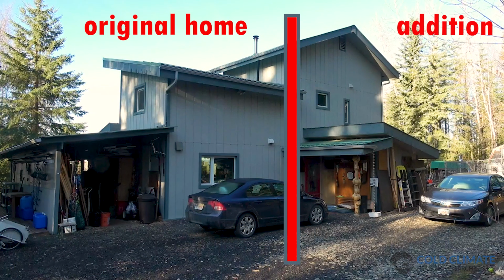A two-story addition was added onto the existing home, and for years afterwards, in the wall and the roof, between the two structures, moisture problems were occurring in the wintertime, and there's been at least 2 attempts, expensive attempts, to try to address this air leakage. And so far, all of these attempts have failed, and there have continued to be moisture problems due to air leakage in the roof and the common wall between the two homes.